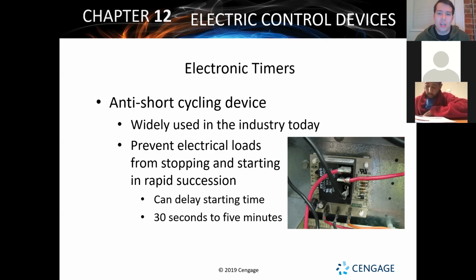For us, what happens when we're short cycling is the motor is taking on more and more electricity, and it's not being given time to dissipate all of that electricity out of it. With that electricity comes heat. So it builds up electricity, builds up excess heat, and the system just burns itself out. That's a very common thing when it short cycles. One of the common problems that comes out of short cycling is a grounded out compressor, which means you have to get a new compressor, which means the heart of your system is getting replaced.